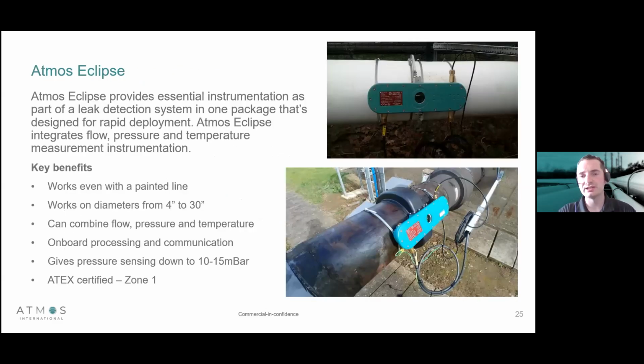The next challenge, as I said, is how do we get instrumentation onto pipelines where we need it or where the customer needs it? So we've developed what we call the Eclipse unit. And this is a non-intrusive solution that provides all the instrumentation we need to provide an effective leak detection system. It combines non-intrusive pressure, flow, and temperature, and it clamps onto the pipeline. We currently can work on diameters 4 to 30 inch. It's fully ATEX certified. We can bury it if we're concerned with tampering. It has all the onboard processing and communication solutions we need, and it can work on even painted lines. This has allowed us to now be able to provide solutions to very remote pipelines or to pipelines that just didn't have any infrastructure in place.